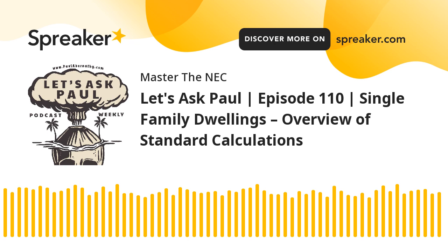Because that's the minimum. It's got to at least be that. So it looks like now we could actually go with a 2-aught instead of a 3-aught. A 2-aught's good for 175. So easily it's going to be at least 83% in sizing, okay, of the service rating. Makes sense? All right. And for aluminum, same concept.